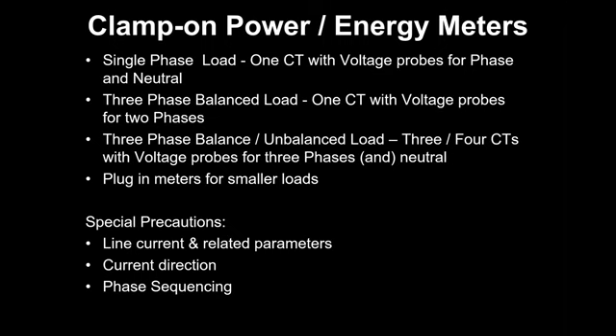So there are some 3-4 types of energy meters available. Now, for a single phase load, that is basically the 230 volt supply and a neutral, there are instruments with one CT and a voltage probe for neutral and phase. So it is very simple. You have a CT, and here again, in most cases we want to do the measurement without disturbing the operations. Every time, suppose for connecting a CT you have to stop the machine and disconnect the cable, it is not possible. So these are all clamp-on type meters, with one CT and two voltage probes, one for voltage and another for neutral. That is a common instrument used for measuring single phase load.